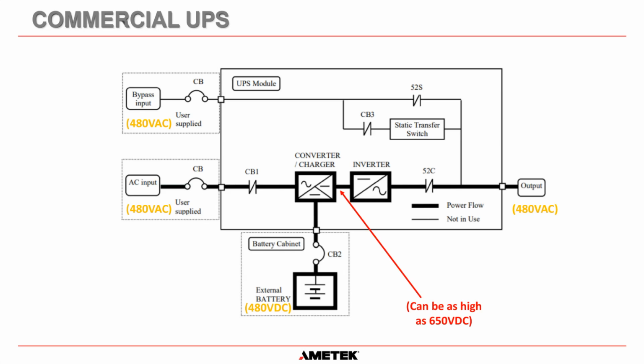So here's a block diagram of a commercial UPS. Okay, and what you'll find is for a commercial UPS, these are not the UPSs that AMETEK Solidstate Controls makes, but they are out there and they are used sometimes in the industrial world. And you can see we have our AC input here, which is usually 480 volts AC. And then they call this CB1. This is actually a contactor in this UPS. And then that goes into a converter charger. So this is converting AC on the left to DC on the right, but it does it a little bit different from a normal industrial UPS system.